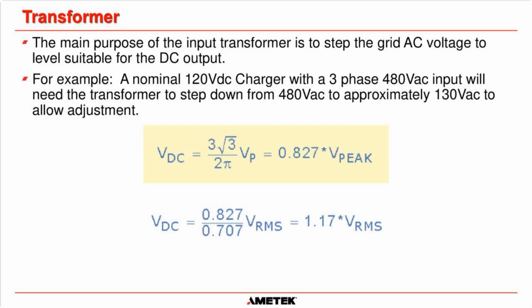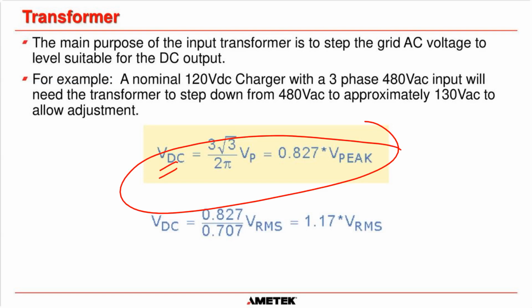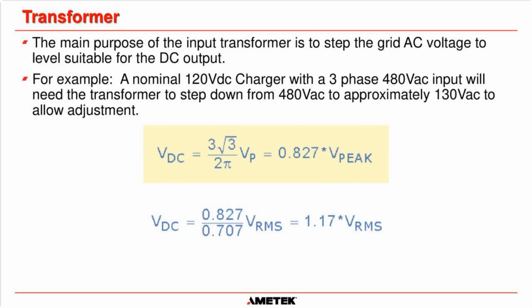This is basically how to work out the average volts DC - it's a well-known engineering calculation. Volts DC is equal to 1.17 times the volts RMS. So if we have a nominal output of 120 volts, and the secondary is 130 volts, we times that by 1.17 - let me do the quick math on my phone because I'm not intelligent enough to do it in my head - it comes to 152.